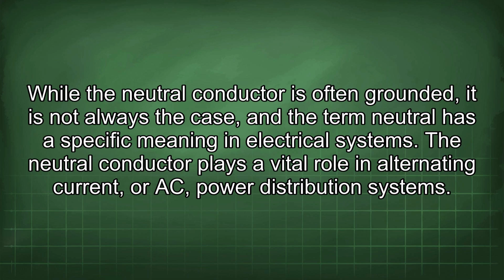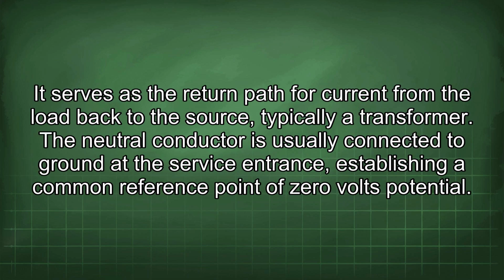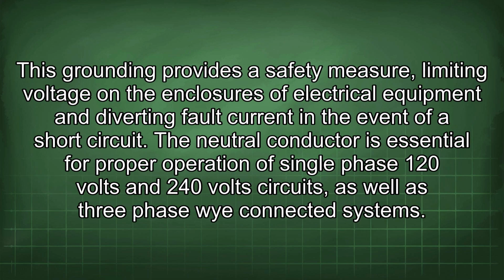The neutral conductor plays a vital role in alternating current, or AC, power distribution systems. It serves as the return path for current from the load back to the source, typically a transformer. The neutral conductor is usually connected to ground at the service entrance, establishing a common reference point of 0 volts potential. This grounding provides a safety measure, limiting voltage on the enclosures of electrical equipment and diverting fault current in the event of a short circuit.